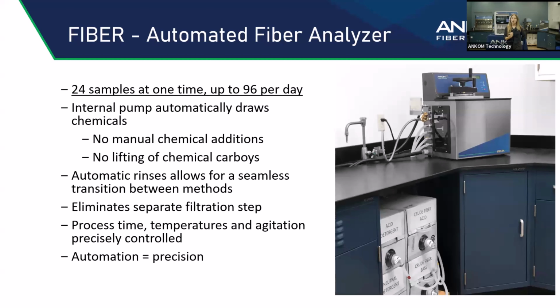So whether that's your crude fiber base, your crude fiber acid, your acid detergent, your neutral detergent, all four of those can be hooked up to the instrument at once. The instrument will know, based on your selection, which chemical to pull for the run. Everything is done automatically. The rinses are done automatically. In between your runs, the valves and the tubing will be flushed, so you'll be ready for your next run. And all of this is time, temperature, and agitation controlled because it's a closed system.